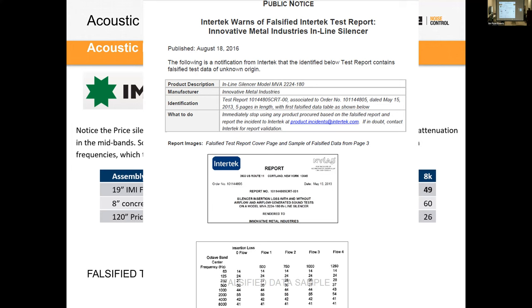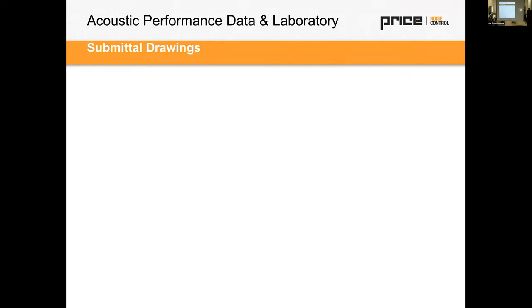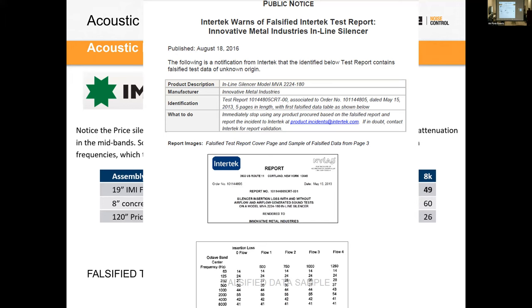And this is tough to see, and I apologize, the image doesn't come through super well on the screen. Maybe you can see it better in there. Actually, it comes up quite clear on the screen. They had 14 dB at their 63 hertz, but they conveniently added that full tolerance range that was allowable in the previous ASTM standard, which isn't really a good way to do things. You're not going to get 30 decibels of insertion loss. They basically took the outer range of the tolerance in the ASTM standard and completely applied it to their performance data and cataloged it. So yeah, that's not what you should do. It's really giving you outlandish results.